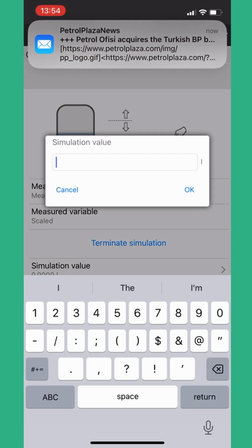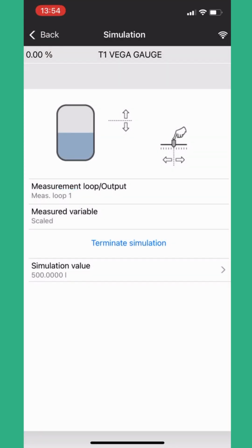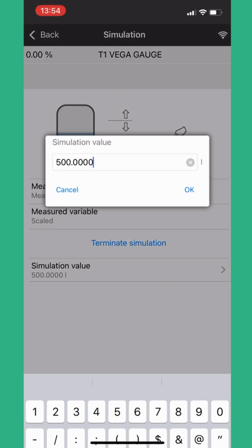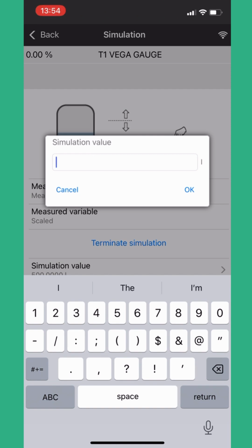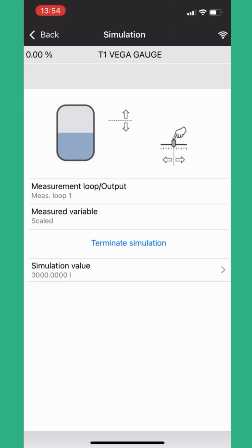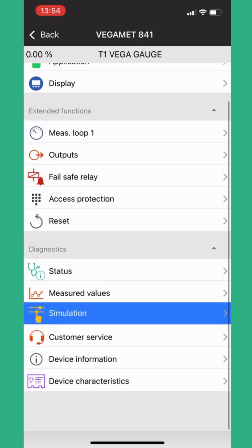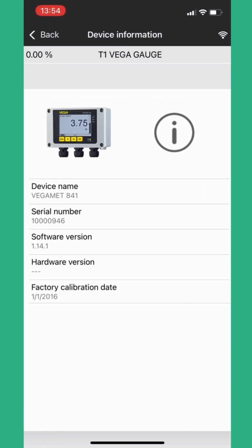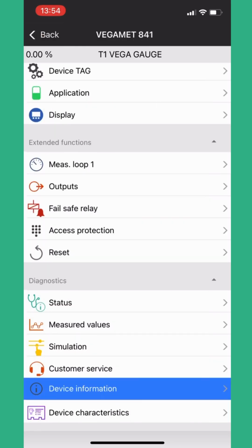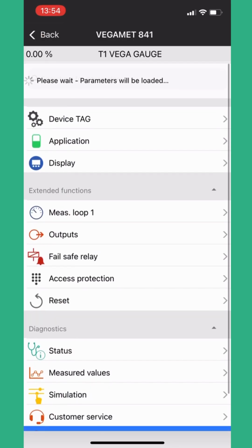And we simply click on the simulation value, change the value to the value that we want to simulate, in this case 500 liters, and the gauge will show 500 liters, and all of the relay switching will also be activated by this. So if we've set the gauge to trigger relays based on a height of 2,900 liters, we can simulate 3,000 liters and see how the relays interact.